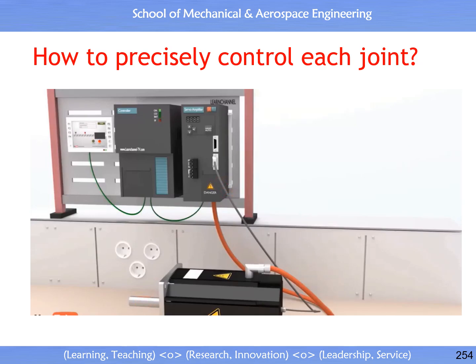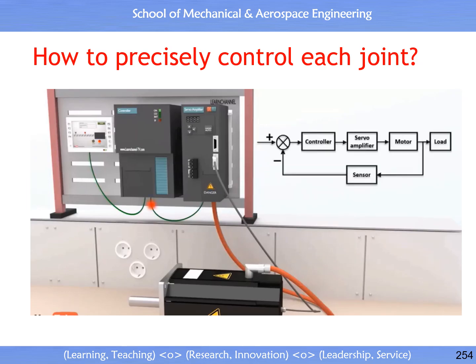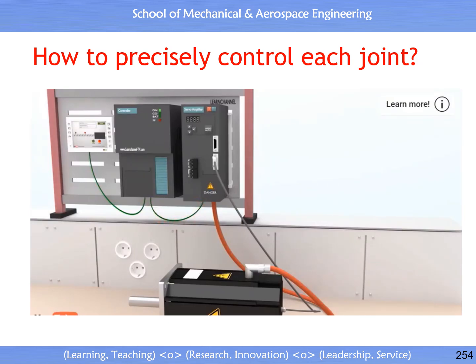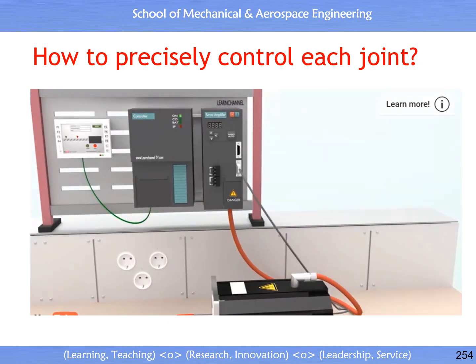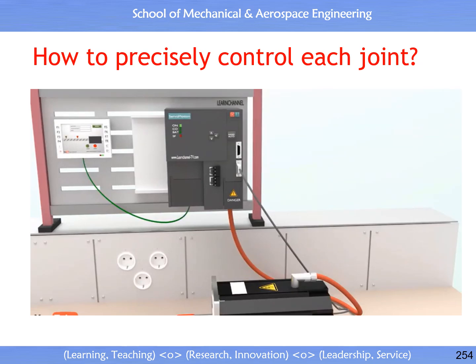The job of the servo motor controller, also named the motion controller, is to close the loop on the system by constantly interchanging data with the servo amplifier. The motor parameters like torque, speed, or position can be adjusted immediately. Some manufacturers offer modules, which combine the controller and the amplifier, so you would have fewer parts, fewer connections, and a smaller footprint.